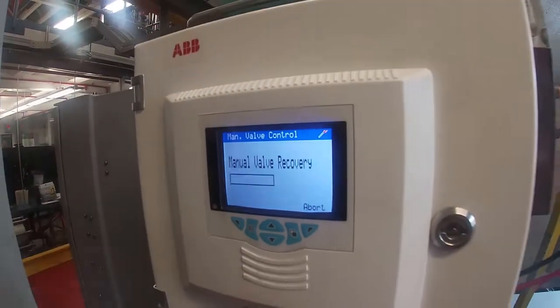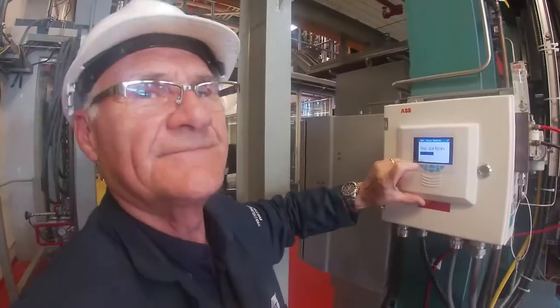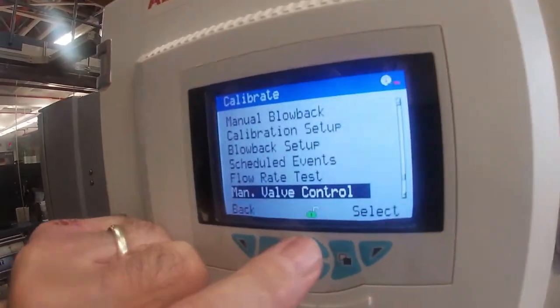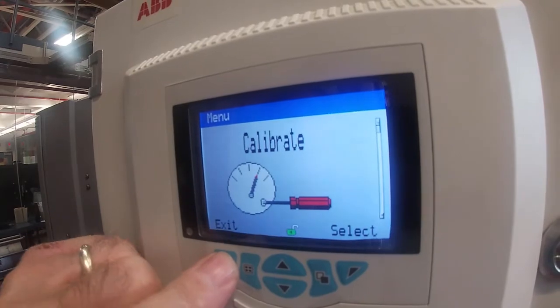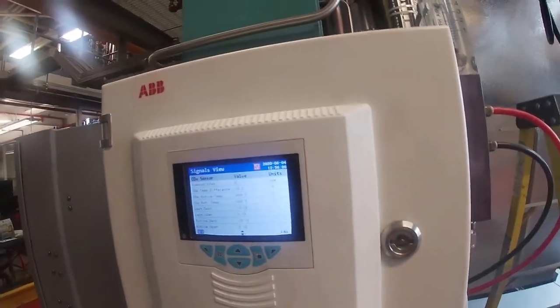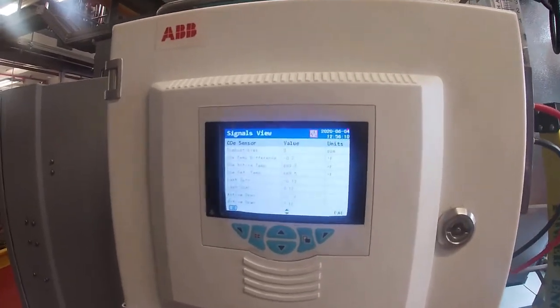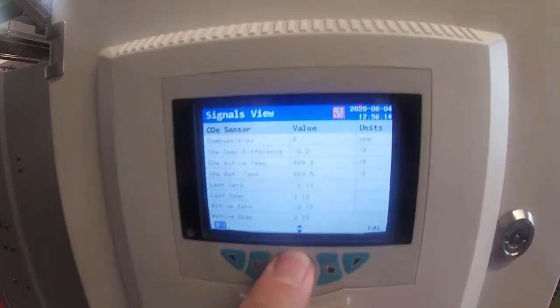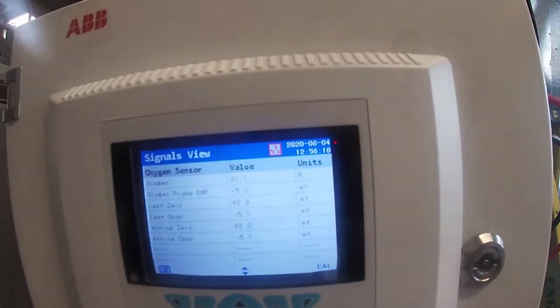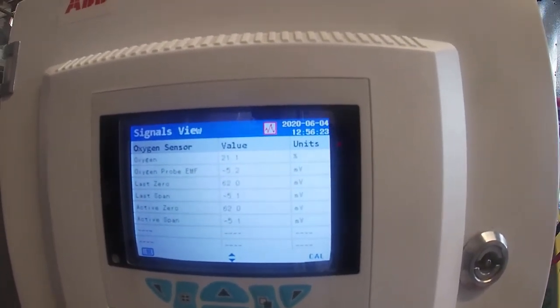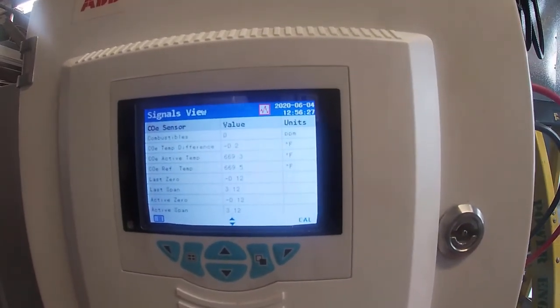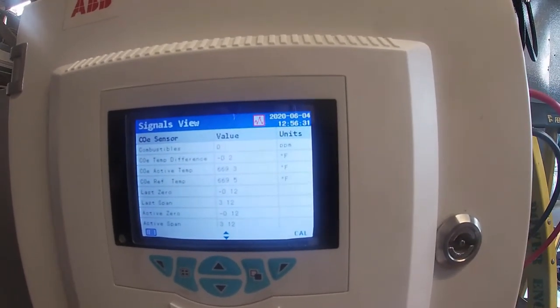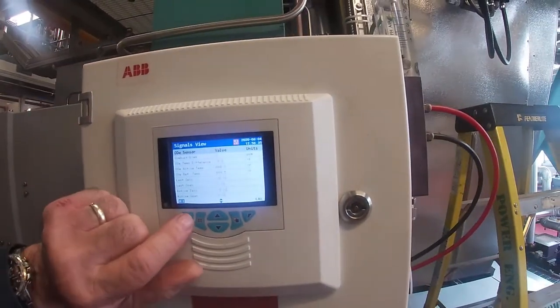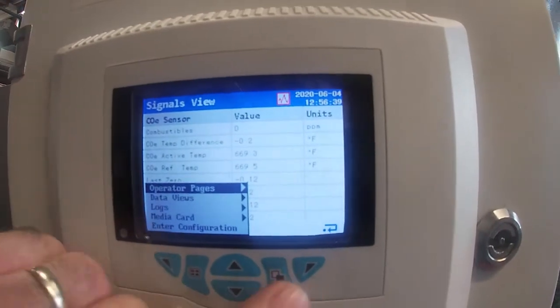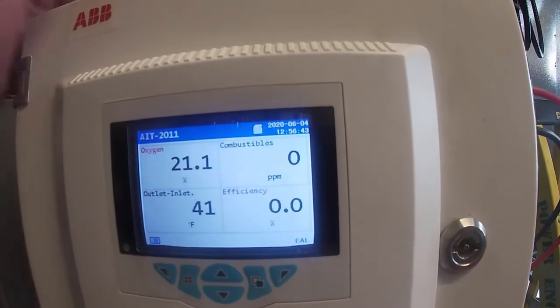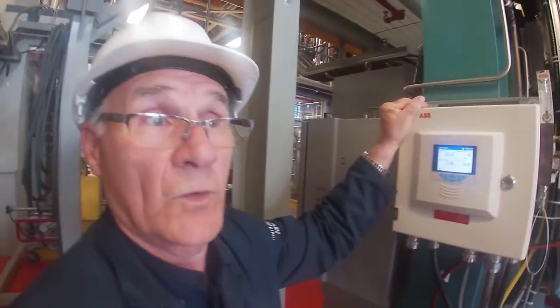So now what I'm going to do is go next, and next I'm going to go right back past the span test and wait for it to come back out of manual recovery. Our manual valve recovery is complete. I'm going to go next, and I'm basically going to get out of here. We've done the calibration. I'm going to exit that, and I want to now look at my signals view and my O2. According to this, oh, that's CO. Let's go back to O2. The O2 sensor is at 62, which is the last recorded value I had for 0, and span is minus 5.1, which is the last value. And if I go down to the CO page, it was minus 0.12 for its 0 value and 3.12 for its active span value. So that's the calibration complete. I'm going to go back to page 1, which is the operating screen, and there we sit. Okay, and so we are basically done the calibration.